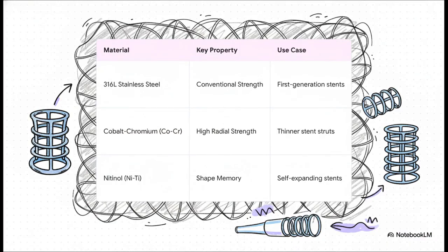Let's just take stents, for example. The metal you choose is absolutely critical. The first ones were made of 316L stainless steel, a good, reliable workhorse. But then came cobalt chromium alloys. These have a much higher radial strength, which means you can make the walls of the stent way thinner, making it more flexible. And then you have the true game changer, nitinol.